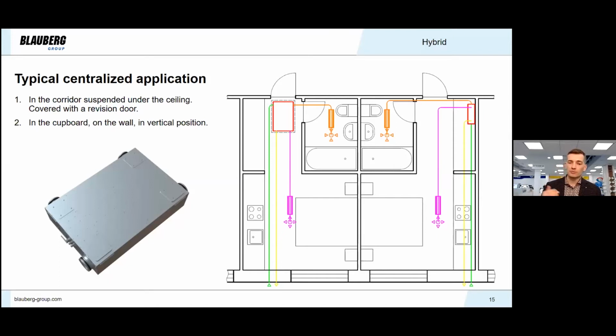In the right apartment, the hybrid unit is installed in the wardrobe in the corridor. It is hanged on the wall in a vertical position. The same flexible adjustment of the spigot location makes it possible to connect all the ducts from the ceiling in a compact manner.